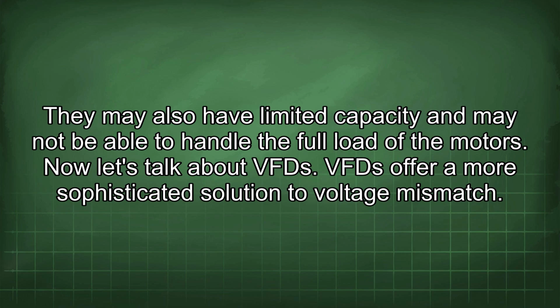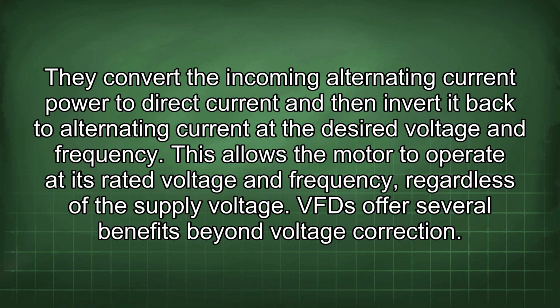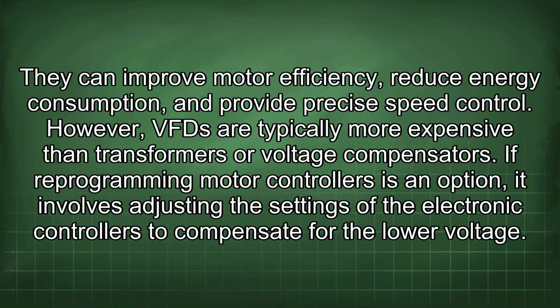Now let's talk about VFDs. VFDs offer a more sophisticated solution to voltage mismatch. They convert the incoming alternating current power to direct current and then invert it back to alternating current at the desired voltage and frequency. This allows the motor to operate at its rated voltage and frequency, regardless of the supply voltage. VFDs offer several benefits beyond voltage correction. They can improve motor efficiency, reduce energy consumption, and provide precise speed control. However, VFDs are typically more expensive than transformers or voltage compensators.